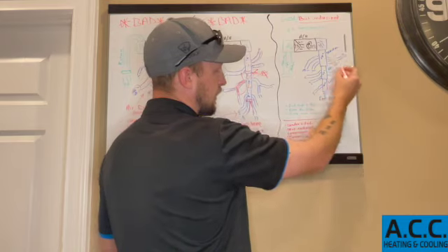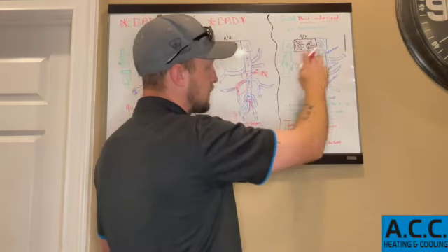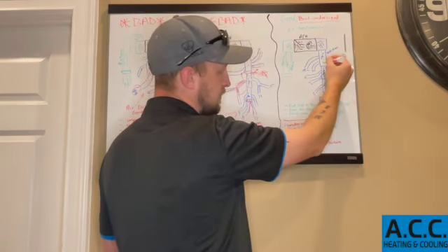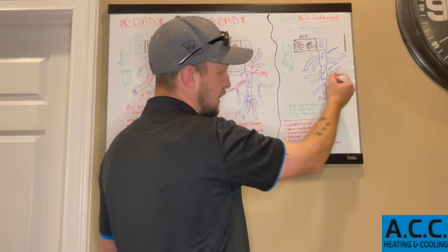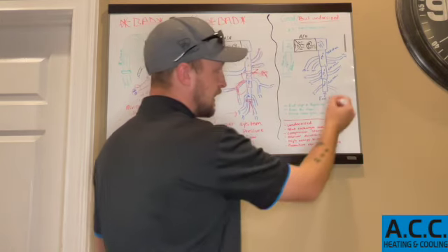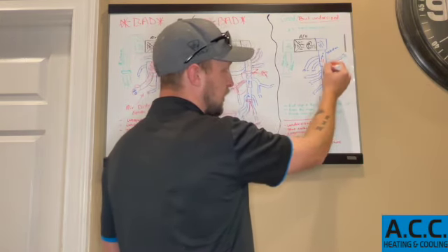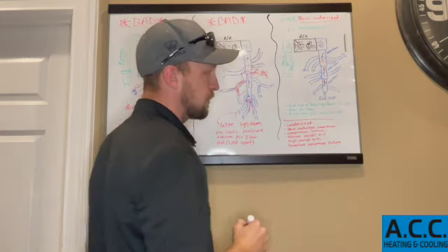So this is the way it's supposed to be. You have a 2.5 ton system here. This 14-inch comes off. This is all hard pipe. The 14-inch tapers down to 12, and then this tapers down to 10. This builds up pressure. If you can imagine all this air coming in and then going into a smaller pipe, and then into another smaller pipe, it builds up pressure.